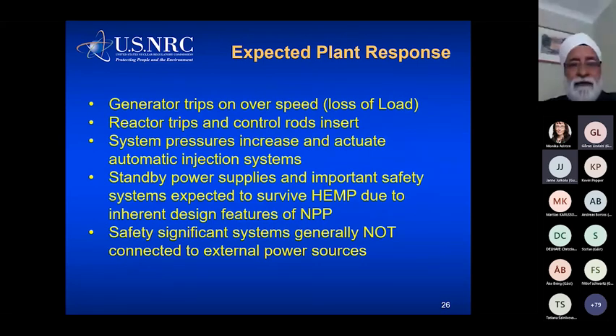Okay, so what happens to the nuclear power plant? We expect the generator to trip on overspeed. All the other trips have failed. When the generator trips, you're going to get a reactor trip, and the control rods insert. We expect the primary and the secondary system pressures to increase and automatic actuation of injection systems. Now, the automatic actuation may or may not take place, but irrespective, if they don't, we can take manual actions.